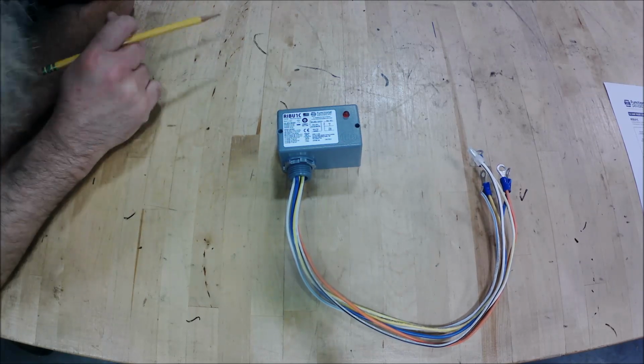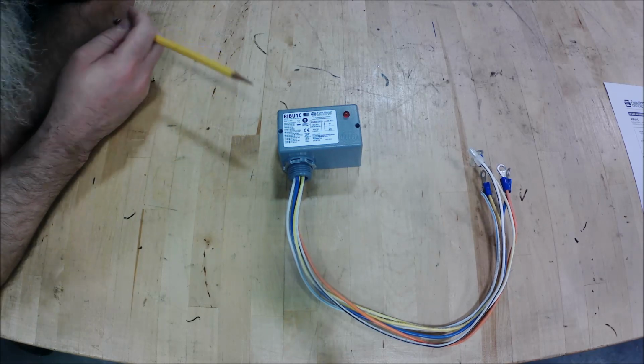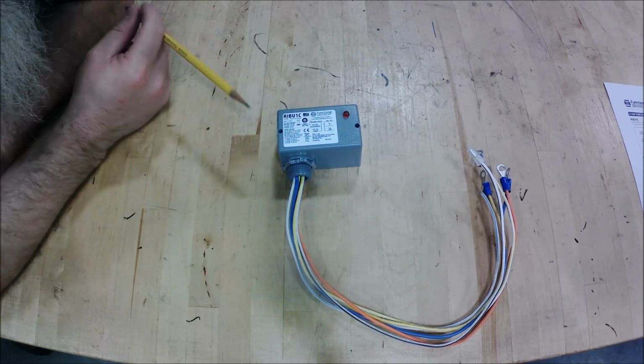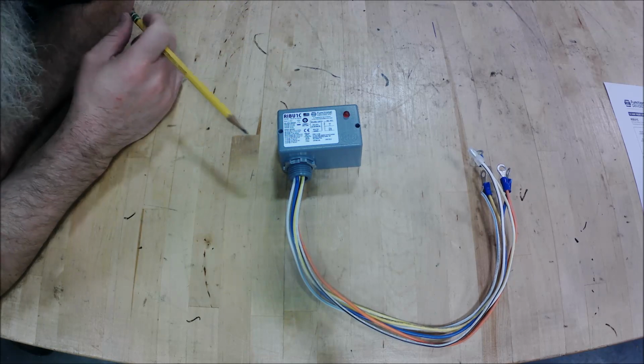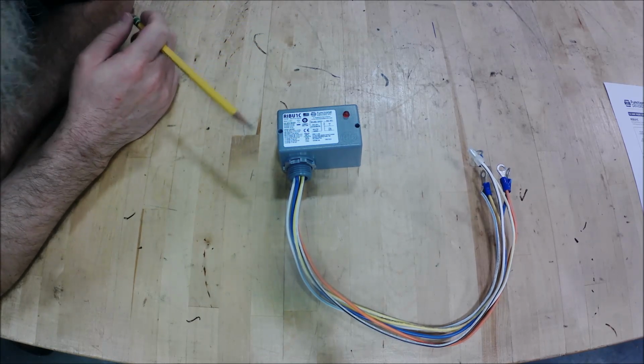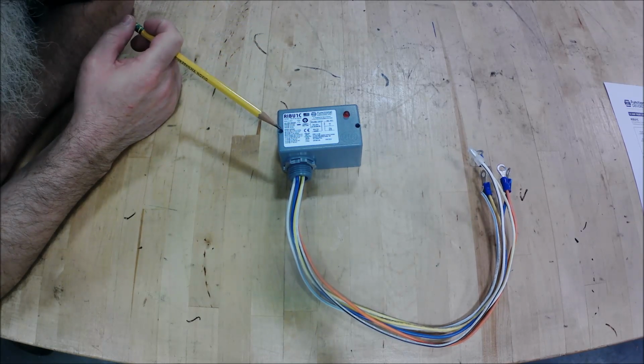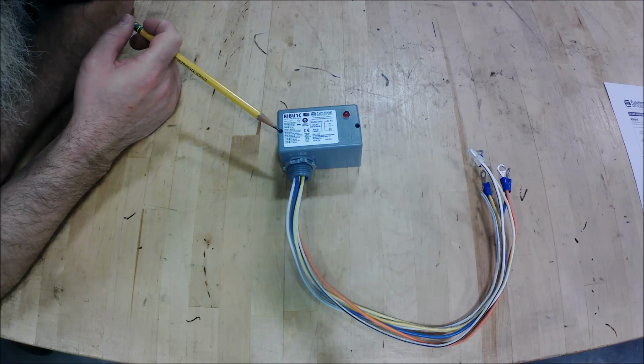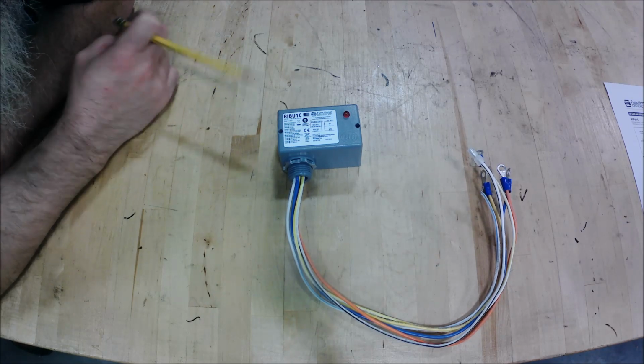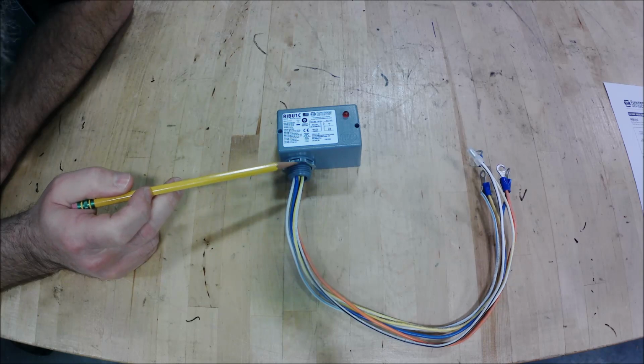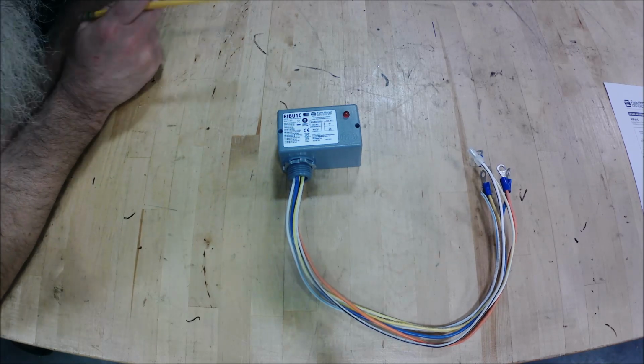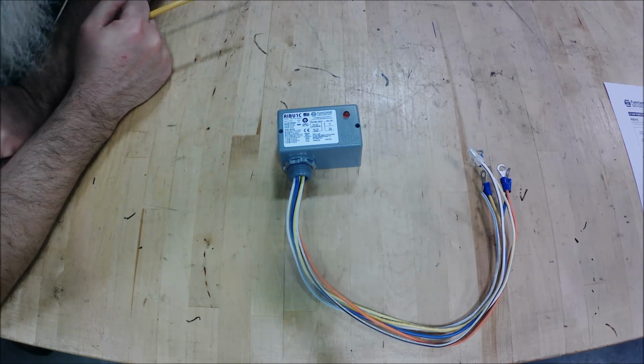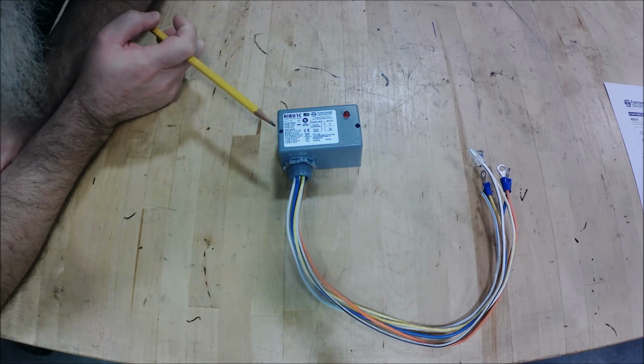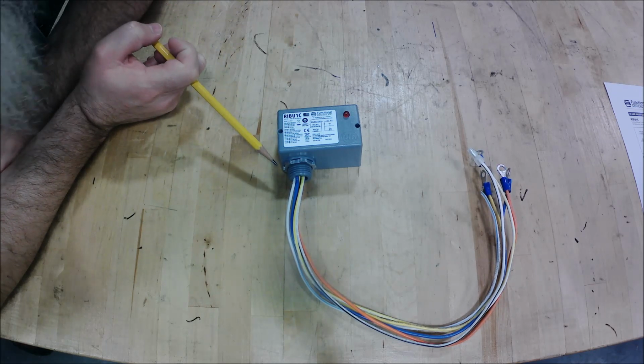So I like it because you can mount it into the side of the unit with screws. They give you 2 screws, probably about 2.5, 3 inches long, probably 2.5. But I can drill a pilot hole and mount them inside a unit, or I can mount them on a panel or through one of the knockouts on the side. I've seen it in the building we're in and on jobs that I've been to out in the field. This is mounted to like a junction box.